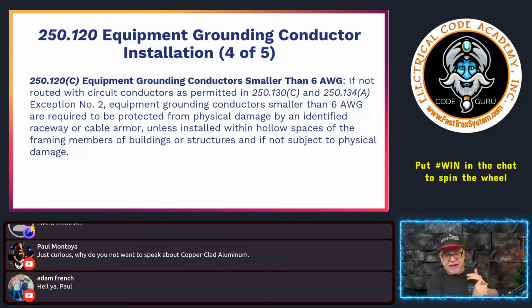One of the options, you can protect a circuit that has no equipment ground with a GFCI. It's not perfect, but it works. Or you could actually run a separate equipment grounding conductor to that circuit. And that's what 250.130(C) is giving you some guidance on, right? All right. So anyway, it says equipment grounding conductors smaller than 6 are required to be protected from physical damage by an identified raceway or cable armor unless installed within hollow spaces of the framing members of buildings or structures, and if not subject to physical damage.